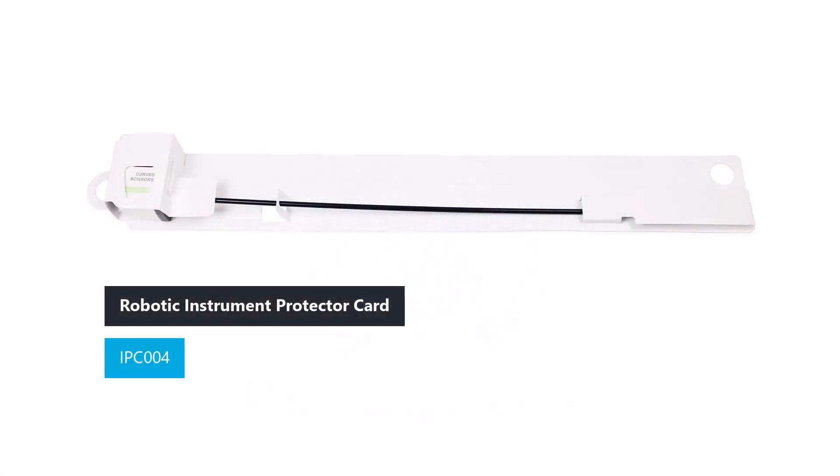Hi, my name is Sharron Rojo and I'm Senior Clinical Education Specialist for Healthmark Industries. Today we're going to show you how to assemble the robotic instrument protector card, which is a mounting surface intended to hold and maintain the item with limited movement for packaging and sterilization.